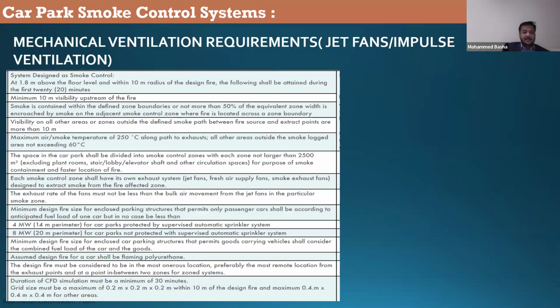Why? Because it is a smoke management system. We need to have tenable conditions. Whereas in the smoke clearance situation, they do not ask you this. They ask you for visibility for the firefighters. The space in the car park shall be divided into smoke zones. This is all general, you know. They mention here 4 megawatts for car parks protected by a supervised sprinkler system, and 8 megawatts when not protected with a supervised automatic sprinkler system. Now, I hope you understand why they're asking 4 megawatts and why 8 megawatts.